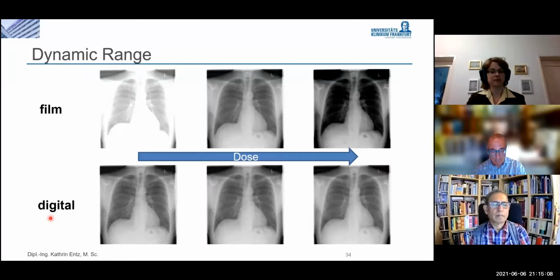And to overcome this problem, a standard exposure index was introduced, and not only the exposure index itself, but also a target value and a deviation index that shows you how much your actual exposure deviates from the target value. The good thing about this standard value is that this exposure index is proportional to dose. So you can simply divide it by 100, at least in calibration conditions. And then you have the dose that your detector receives.